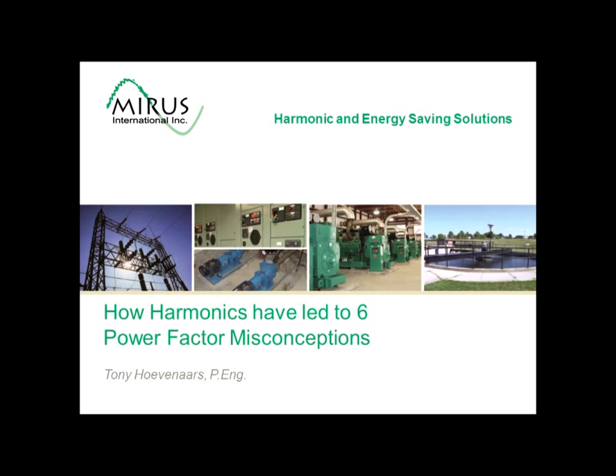Although a low power factor does indicate that a power system is not being effectively utilized, if this occurs only when the system is lightly loaded and the reactive power component in kVAR is quite low, there is no need for concern. Only when the power factor is quite low under more heavily loaded conditions does it need to be addressed. Placing conditions that are too rigid with respect to power factor can lead to installations that are more complex, costly, and unreliable than necessary. And in many instances, a little leading power factor can be effective in compensating for inductive reactive power located elsewhere on the power distribution system.